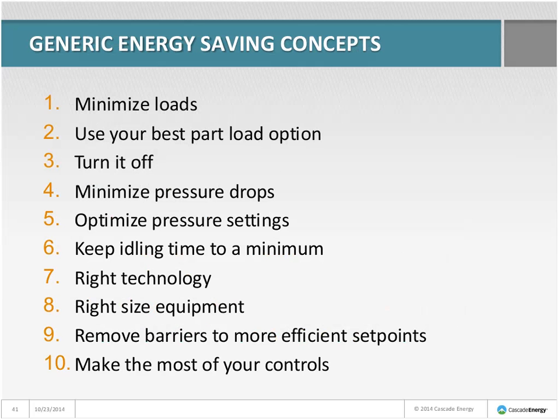Looking at what these guys did to clean up their system: minimize loads on the bag house cleaning; use your best part-load option — the controls upgrade allowed simultaneous trimming; minimize pressure drops and optimize pressure settings by adding the parallel pipe; keep idling time to a minimum — the control system does that automatically.